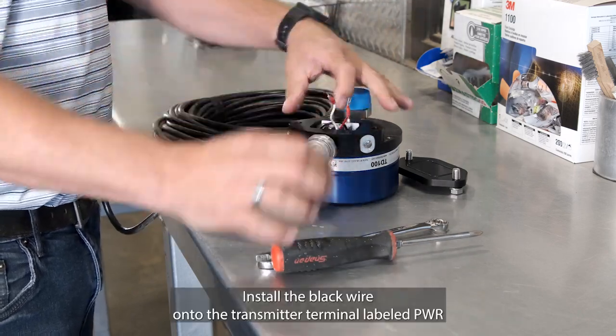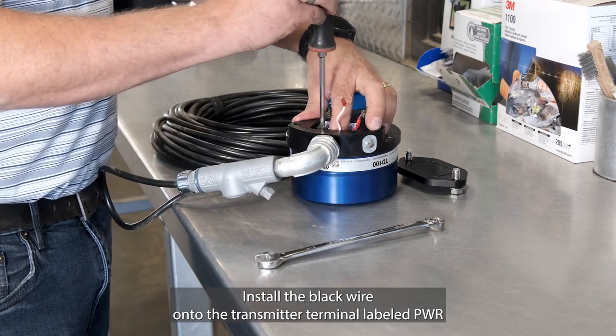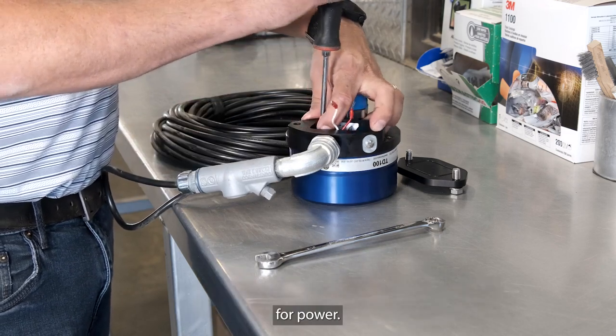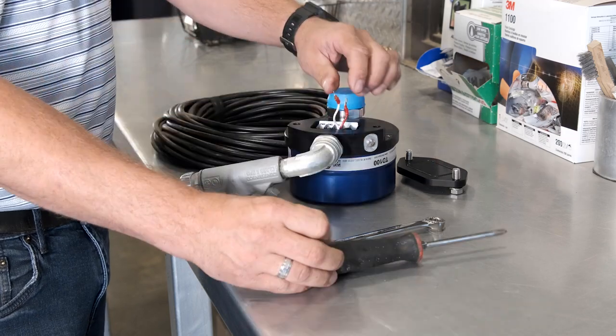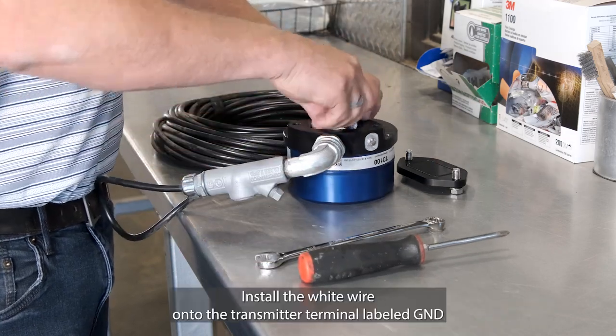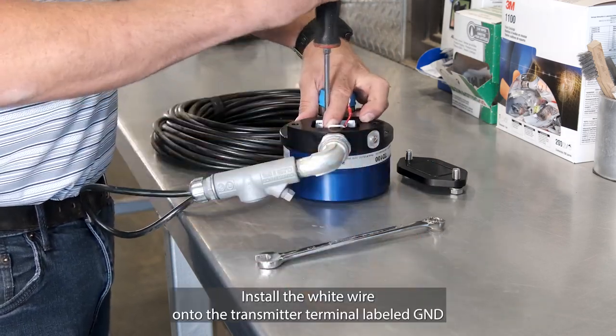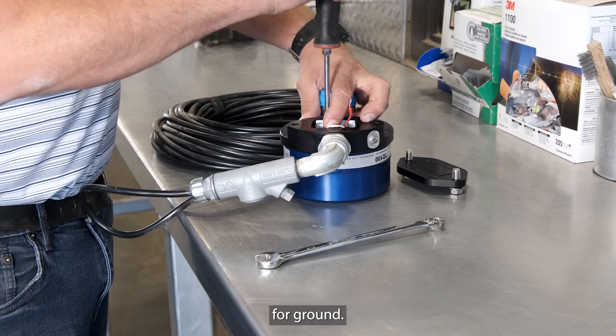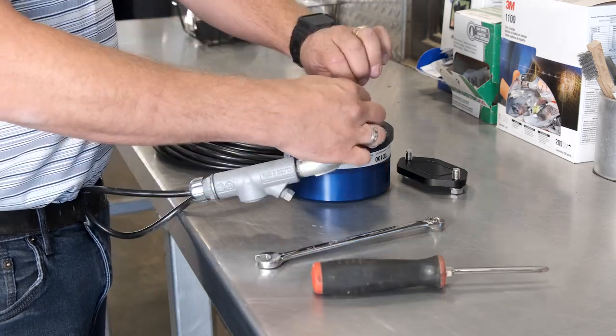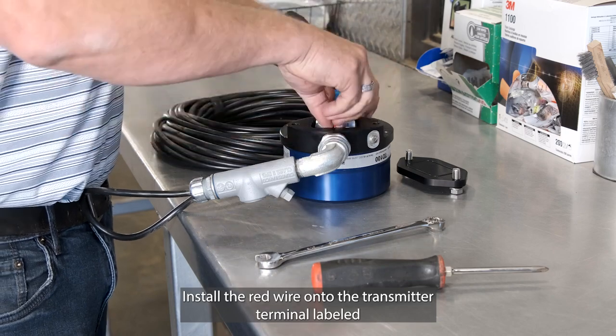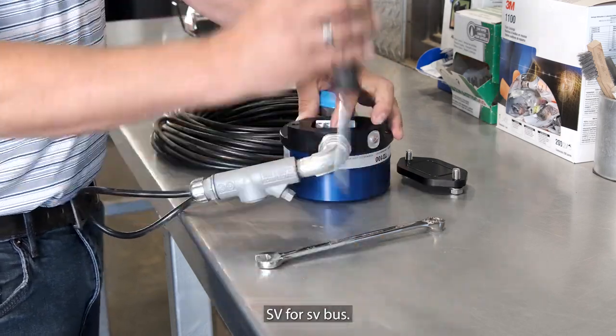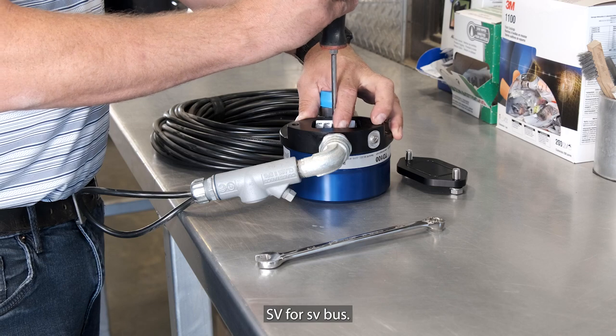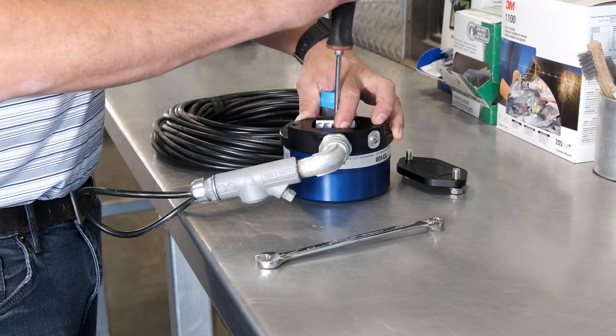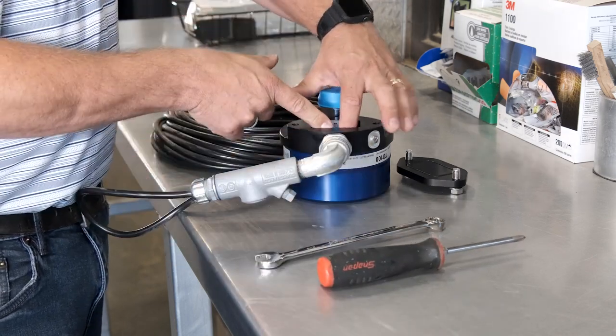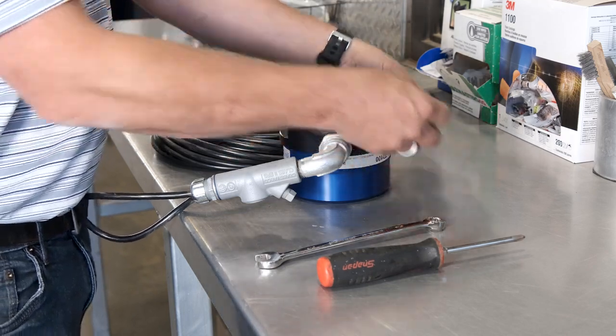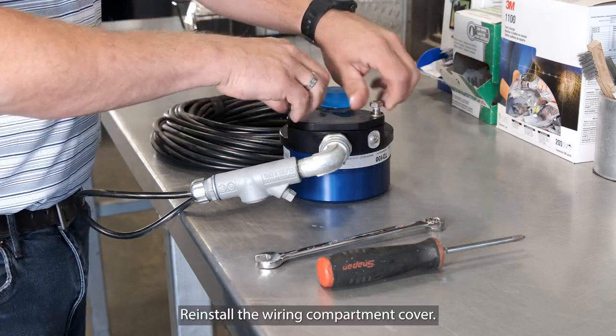Install the black wire onto the transmitter terminal labeled PWR for power. Install the white wire onto the transmitter terminal labeled GND for ground. Install the red wire onto the transmitter terminal labeled SV for SV bus. Reinstall the wiring compartment cover.